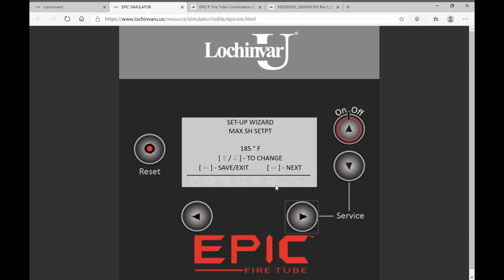The next thing we'll do is go to our outdoor temperature on the coldest day. In the previous setting, we said that on the coldest day we want it to be 120, and this is telling us that at 10 degrees Fahrenheit we want it to be 120. We can adjust this as well. Different climates obviously require colder or warmer temperatures, and this is completely adjustable. But we just have to remember that this is on the coldest day. What temperature do we think, on the coldest day, we're going to set our highest temperature for?